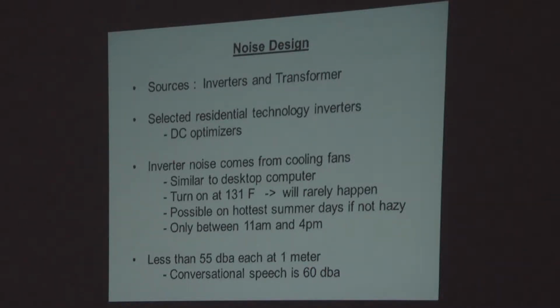But the cooling fans will come on, and they can provide noise, and that's what the noise spec refers to in the data sheet. The cooling fans are muffin fans. They're similar to what you'd find on a desktop computer. In these inverters, they're designed to turn on at 131 degrees Fahrenheit to cool the inverters. And that's because these inverters are typically put inside buildings in rooms that don't have airflow. They can also be mounted directly into the sun, and they're designed for operations where they sit in the sun, maybe even in a desert. So they have these cooling fans that will come on.